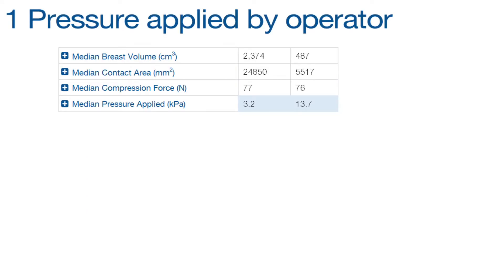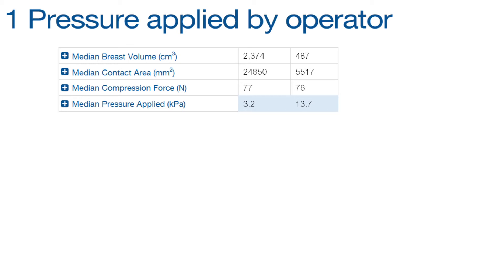Following are examples of how sites have used Volpara Analytics to identify issues and make immediate corrective actions to maintain accurate, high-quality breast care and patient satisfaction. A busy site in the US discovered that one of its operators was routinely applying about 75 newtons force no matter the breast size. As a result, some women were receiving too little compression giving poor image quality and high dose, and others were receiving too much compression giving poor patient experience. We also identified another case where an operator consistently applied too much pressure, which was confirmed with patient complaints.